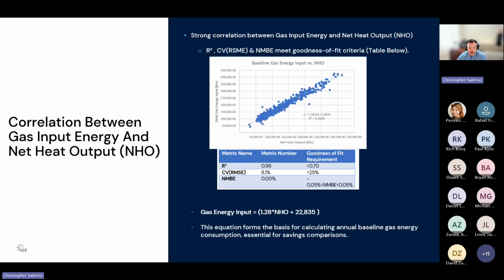So what we had to do to be able to project annual gas energy consumption is we found that the gas energy input tracked very well with the net heating output. And the net heat output is defined as the difference between the supplied hot water energy and the return, the hot water return and cold water energy entering the system. So basically, it is the amount of heat the boiler is putting into the water. Since the net heat output tracks very well with the gas energy input, we can use this to project an annual consumption, to see how much this baseline would consume over the course of a year.